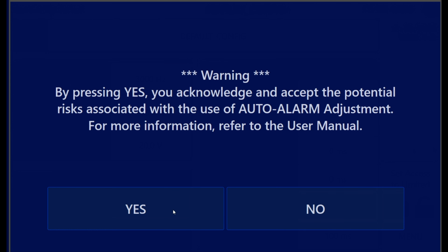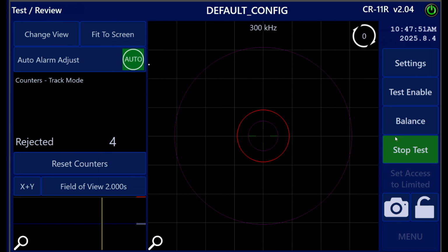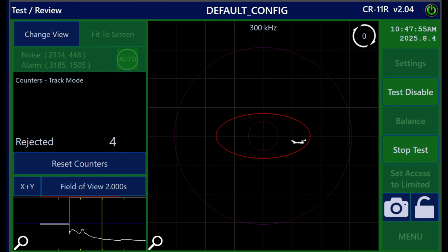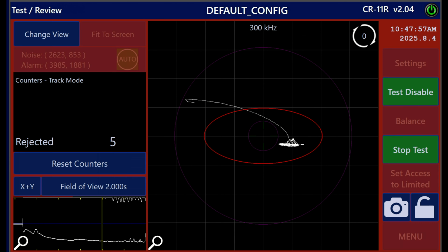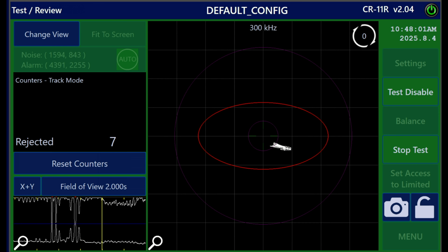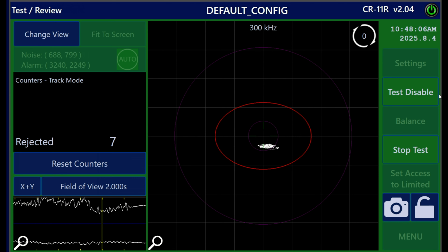Alternatively, and only for very specific applications, auto mode can be used to help identify defects in long runs of material which can slowly change structure as the run progresses. In this mode, the alarm slowly morphs along with the size and shape of the current material noise.